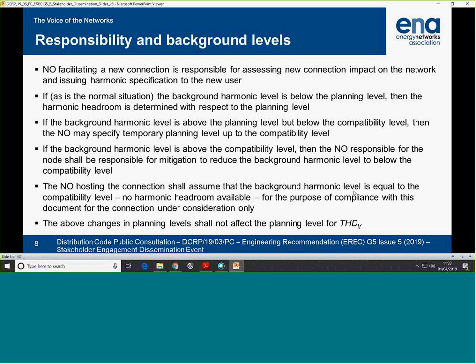When it comes to background, one of the issues we had was that at some nodes in the network the harmonic levels are approaching the planning level in G5-4. What to do with them? Some of them are actually exceeding the planning level and compatibility level. So what do we do with them? We put a guideline within G5-5. The draft which has been published is issue 5.